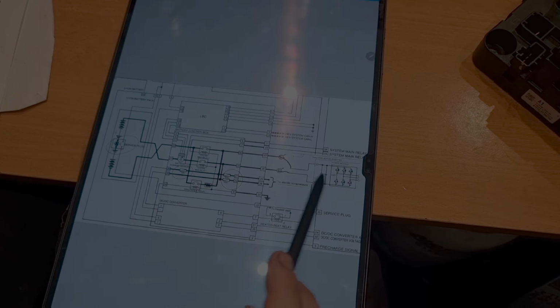A lot of the time we would straight away go, well, hang on a minute, it must be a fuse issue. But if you have a look, the fuses go to the aircon compressor and the DC converter. There is no fuse, other than the one in the service plug which we've checked, that goes to this inverter module. So there isn't a single fuse - even if all 3 of these were popped, we would still expect to see voltage at this inverter. There isn't.